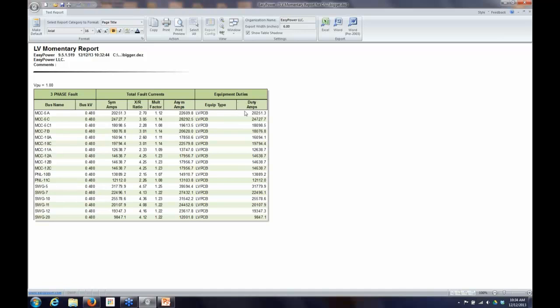EasyPower automatically adjusts the symmetrical amps to get the duty amp value, which you use to compare to the breaker rating. If an adjustment is necessary, it's made here and the duty amp value is compared to what's on the nameplate. Remember the difference between duty and rating: the rating is what comes on the breaker and never changes; the duty is what the breaker is subjected to at a particular point in your system, which varies depending on the bus and other variables.